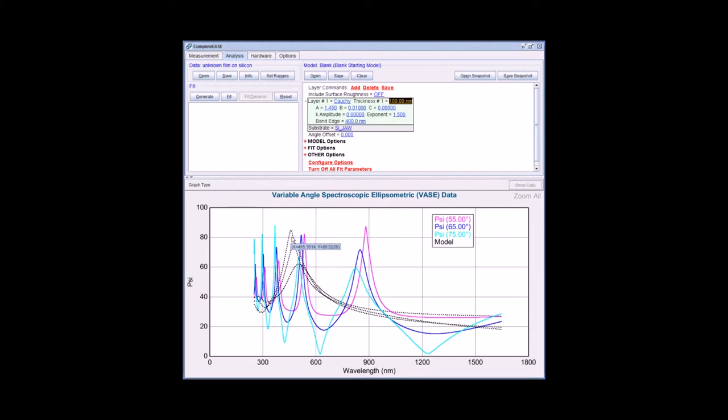The number of oscillations in the data is related to the film thickness. I notice my model generated data has one oscillation, whereas my experimental data has five oscillations. So the starting guess of 100 nanometers is too small. I can hold my mouse over this value, press the shift key, and scroll the mouse wheel up to increase thickness. As I do this you can see the number of oscillations in the model generated curves are increasing. When I get around 560 nanometers, the number of oscillations is a much better match.